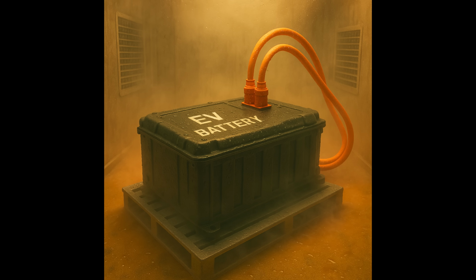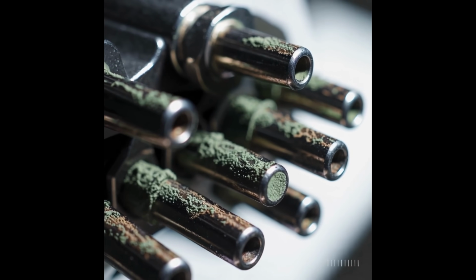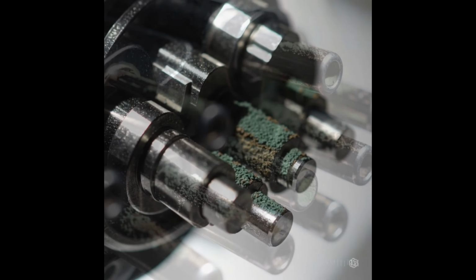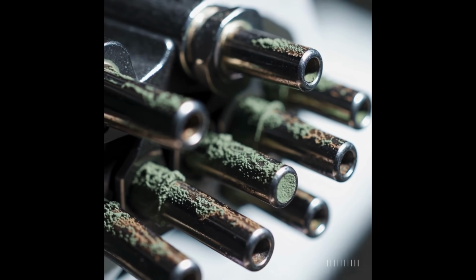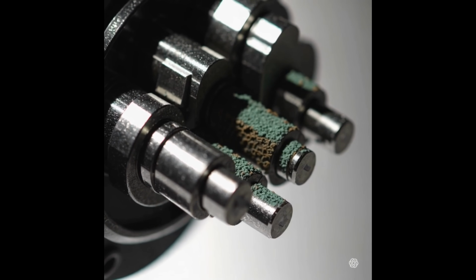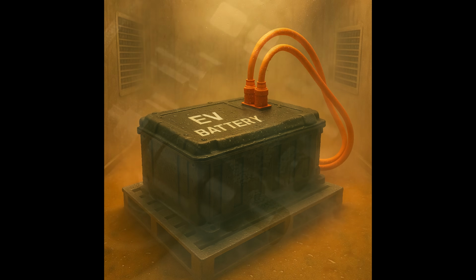Failure risks that we look for during humidity testing include corrosion of bus bars, terminals, or welds, moisture ingress into vented housings, breakdown of conformal coatings or potting, and risk of high voltage shorting. Humidity can turn a minor seal imperfection into a catastrophic short circuit event if moisture bridges high voltage paths.